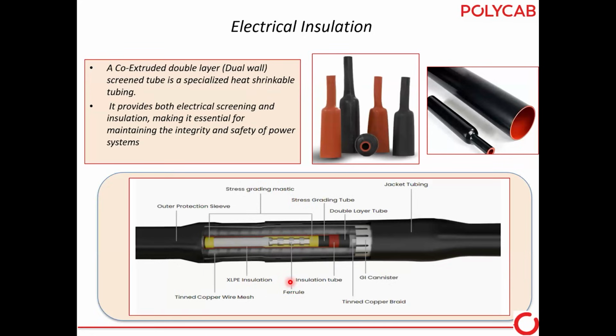Now, let's understand, we are going as per the cable construction only. Whatever cable layers are there, that way only we are going. Like the cable has the conductor, over the conductor a semiconducting layer, over the semiconducting layer XLP insulation, and over that a semiconducting layer. That way only we are also building our joints and terminations. Ferrule, after ferrule semiconducting layer, over the semiconducting layer XLP insulation.